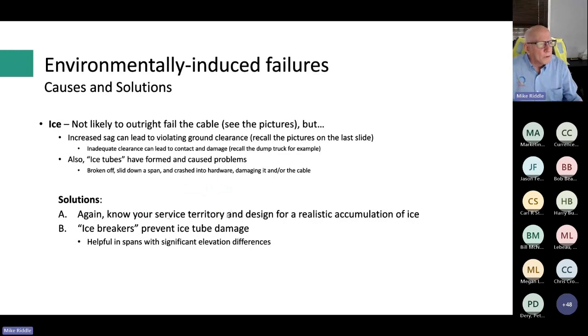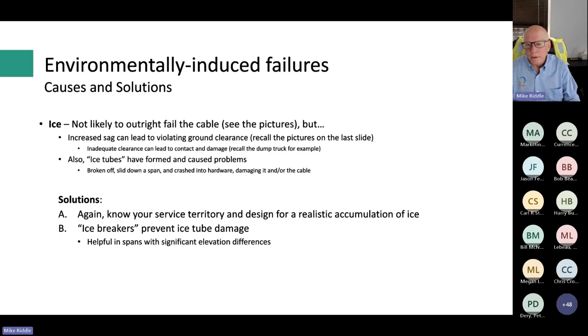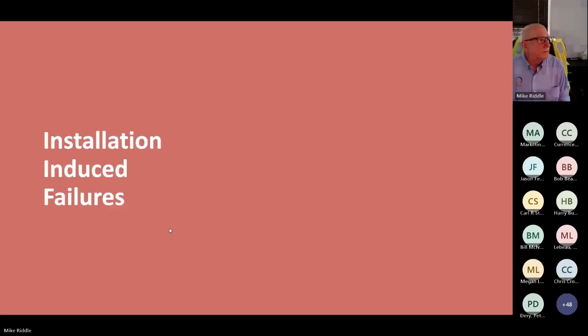The solution for ice is to know your service territory and design for realistic ice accumulation. In mountainous terrain with elevation differences, ice breakers are available on the market that you can install so that if an ice tube slides down, it's much less likely to damage the cable or hardware.